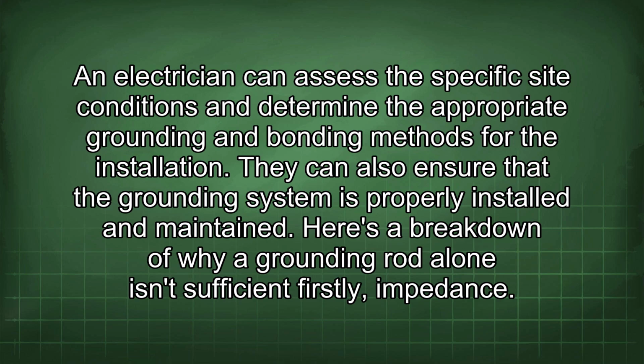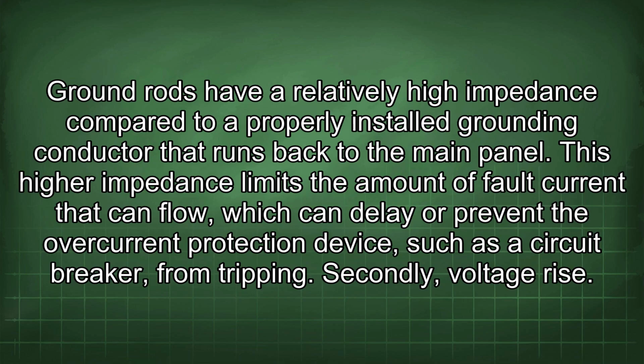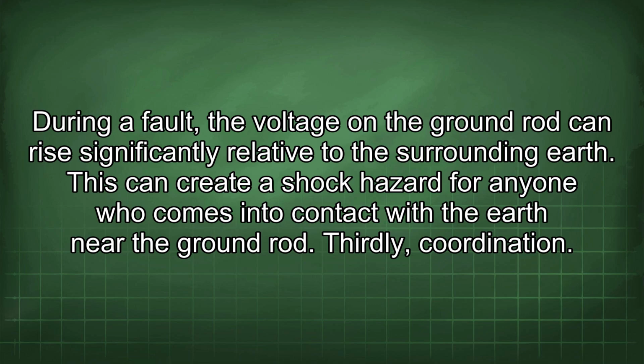Firstly, impedance. Ground rods have a relatively high impedance compared to a properly installed grounding conductor that runs back to the main panel. This higher impedance limits the amount of fault current that can flow, which can delay or prevent the overcurrent protection device, such as a circuit breaker, from tripping. Secondly, voltage rise. During a fault, the voltage on the ground rod can rise significantly relative to the surrounding earth. This can create a shock hazard for anyone who comes into contact with the earth near the ground rod.